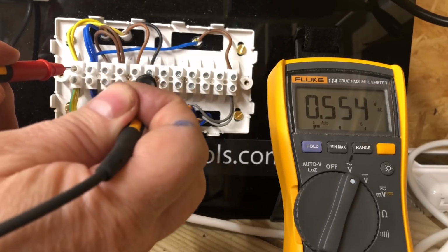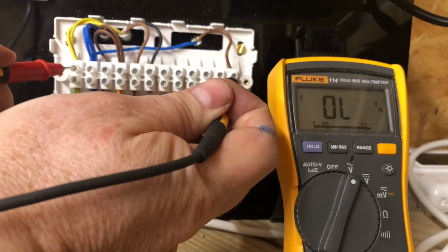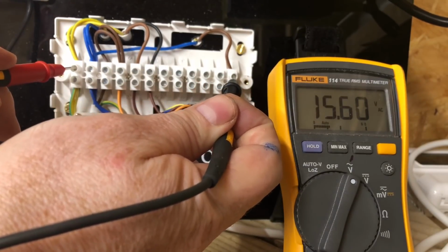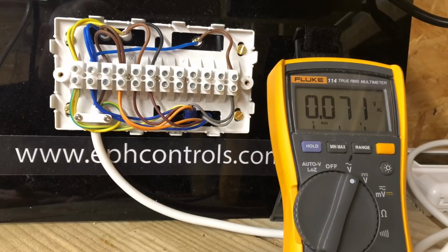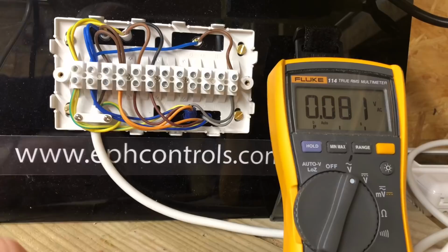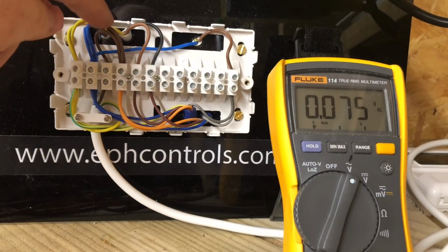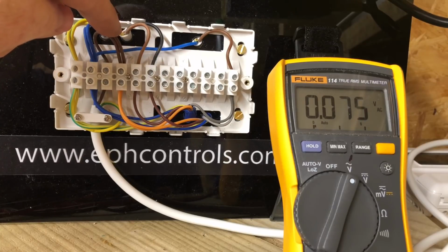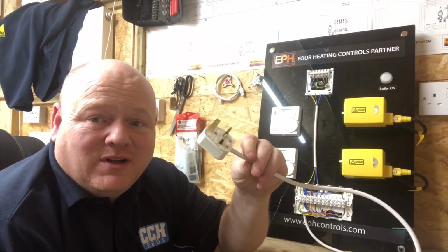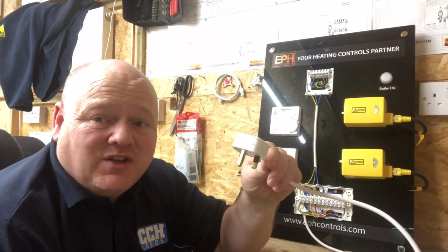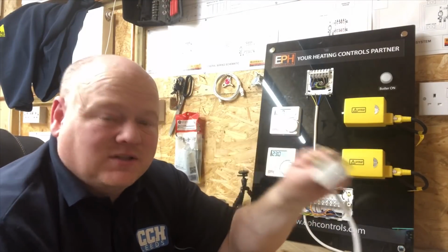If we look on the other wires, there's no voltage on this one, on the brown. There's no voltage on the black. And there's no voltage on there either. So now we'll follow the journey. We've got our live wires here, which we've just got to be careful with because they are live. For the purposes of the video, I've unplugged it, so I've got safe isolation at the moment. We know that if it's unplugged physically, we've got safe isolation.